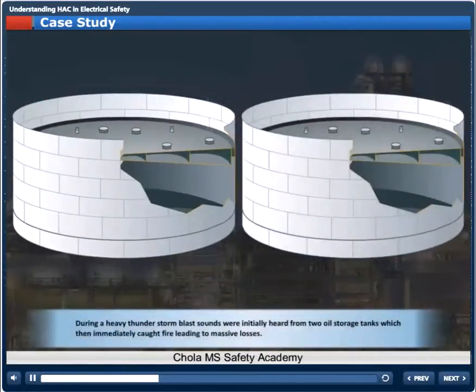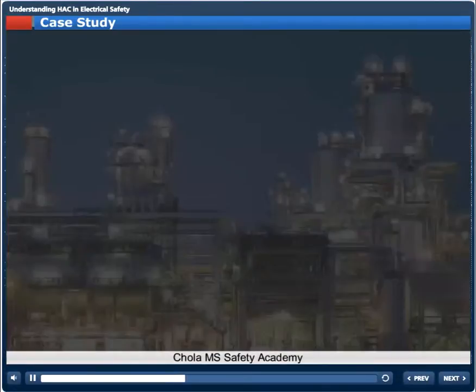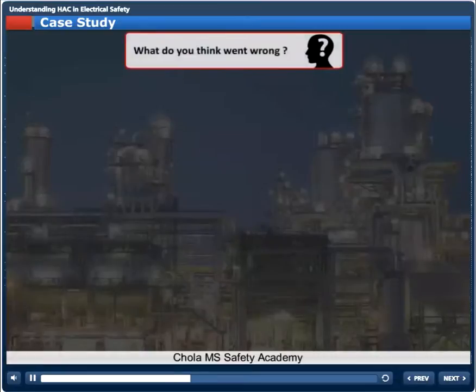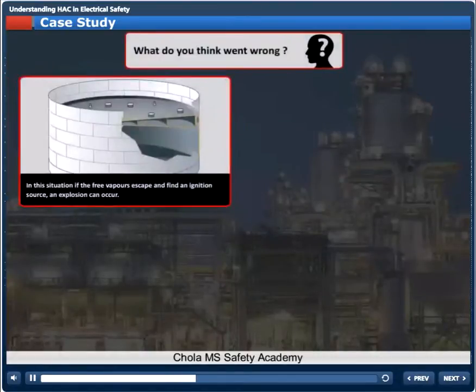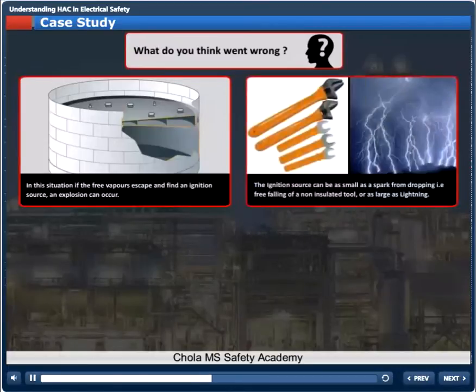During a heavy thunderstorm, blast sounds were initially heard from two oil storage tanks, which then immediately caught fire, leading to massive losses. What do you think went wrong? In this situation, if the free vapors escape and find an ignition source, an explosion can occur. The ignition source can be as small as a spark from dropping, that is free falling of a non-insulated tool, or as large as lightning.